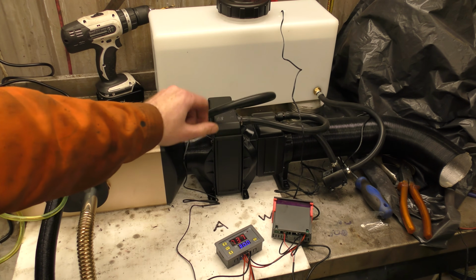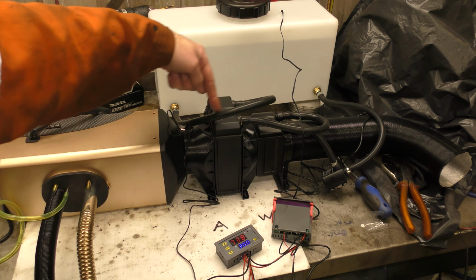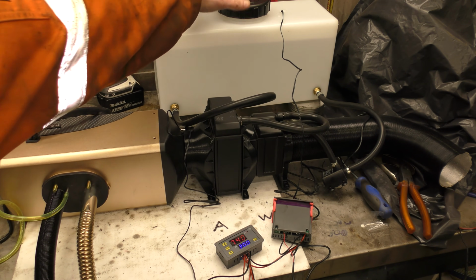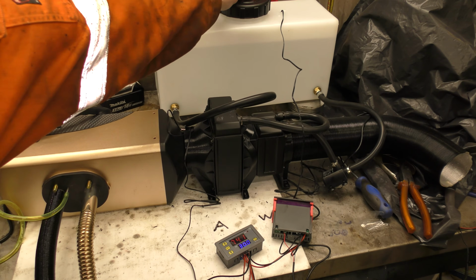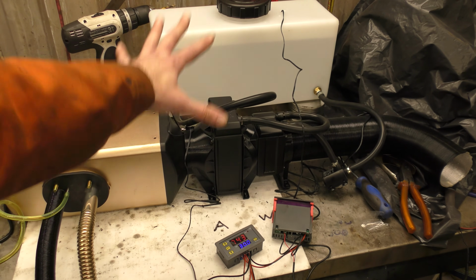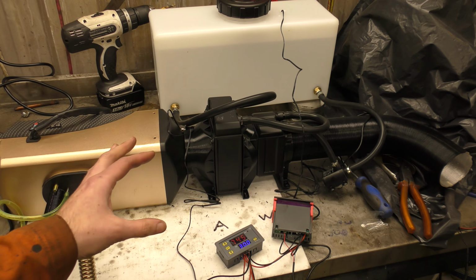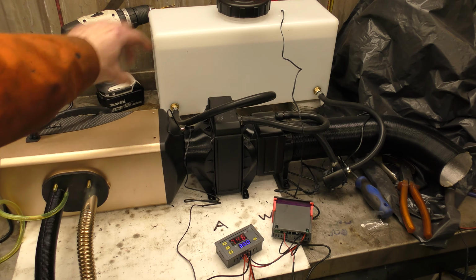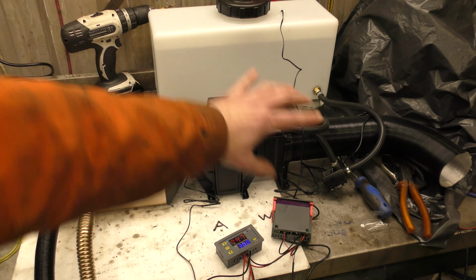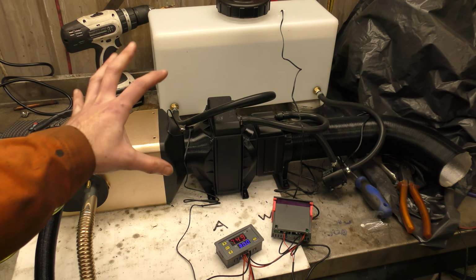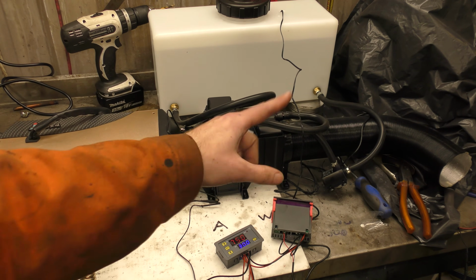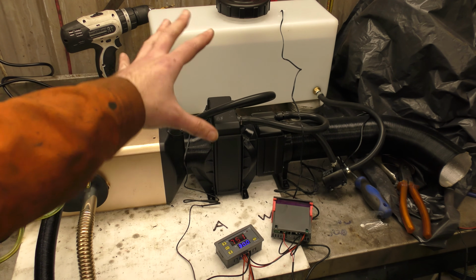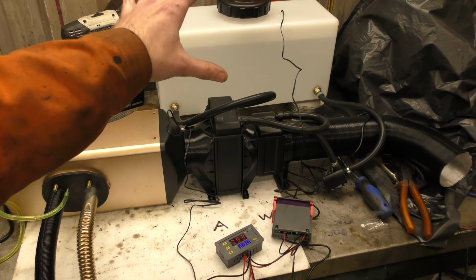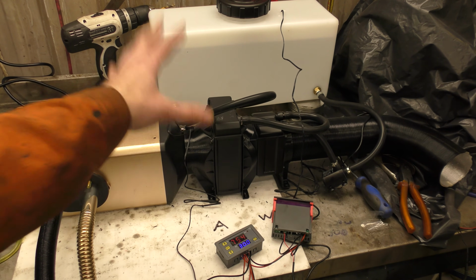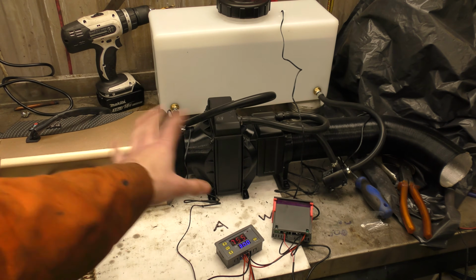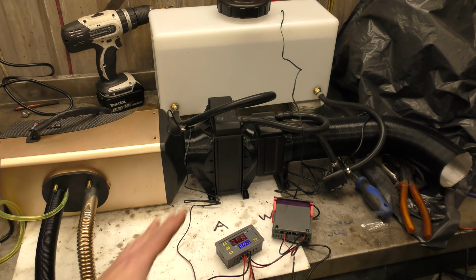The boiling water is still free to boil out of the top here and make bubbles, and this is vented as well. You have to have a sealed setup for things to explode. If everything was sealed - this, the tank - and there was nowhere for the water pressure to go as it boiled, yes, it will blow one of these pipes off. But in this setup, where everything's vented, it will not explode. It will not shoot pipes off, blow pipes off, any of that nonsense. That will not happen.